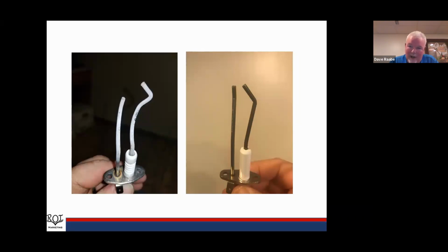So our boilers are shipped ready to go on natural gas. If you're going to put them on propane, you have to convert them. Certain boilers, like the Alpine, it just requires an adjustment to the gas valve. The K2, we actually have to change this venturi that I talked about. So it requires the venturi to be changed. But here was a boiler that was not converted from natural to propane, but it was running on propane. So that boiler was overfired.